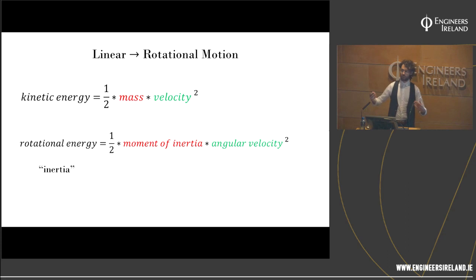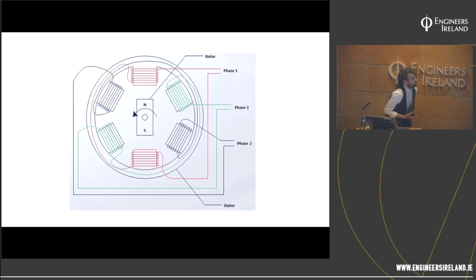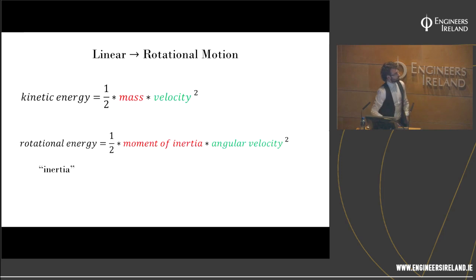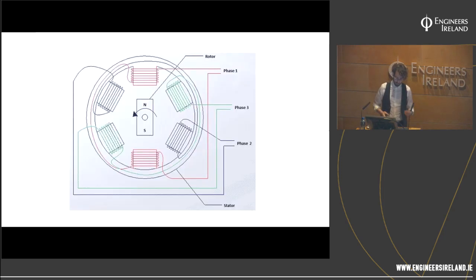When people say inertia, they're really talking about the rotational energy of a synchronous machine rotating once connected to the grid. Why is it important, or why do we care? We know we have energy, but what does that all mean? Well, this is a simplified schematic of a synchronous generator, and the speed of rotation of the shaft is directly coupled to the frequency of current and voltage injection into the grid. What that means is that the mechanical speed of this machine is umbilically linked to the grid frequency, the electrical speed of the system.